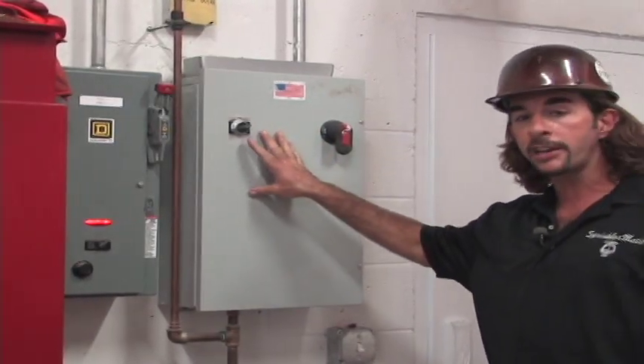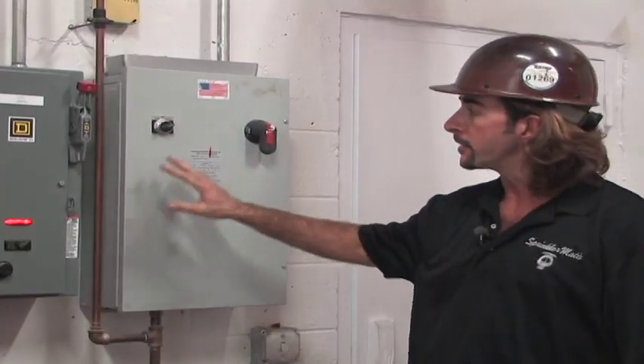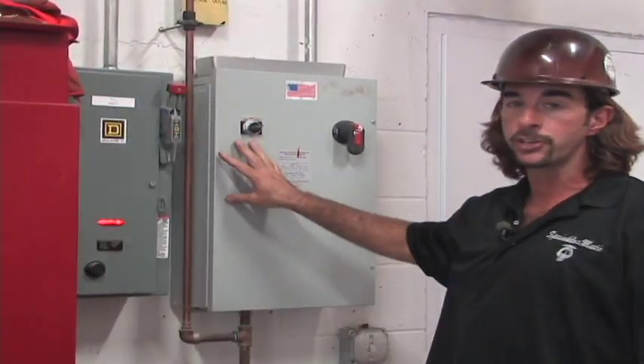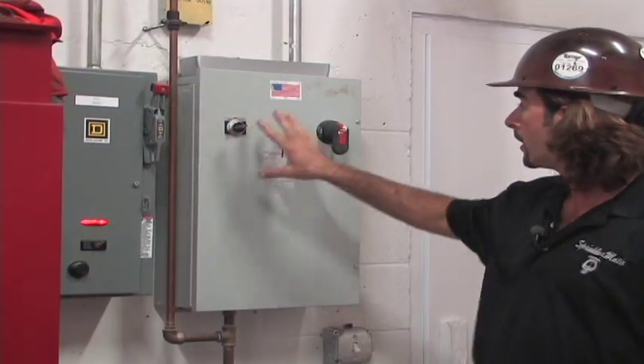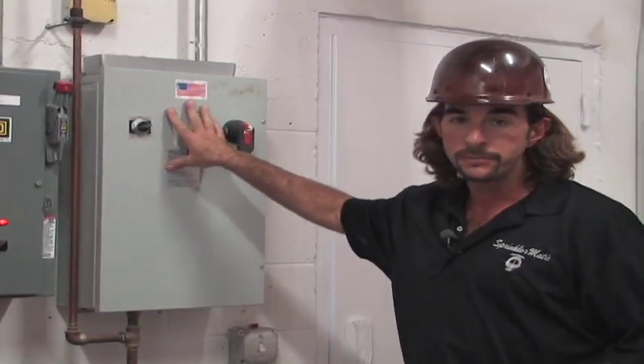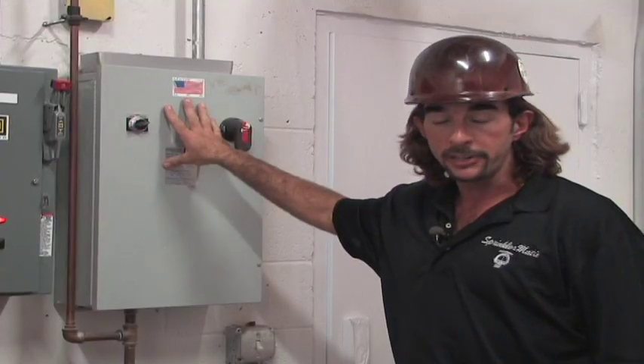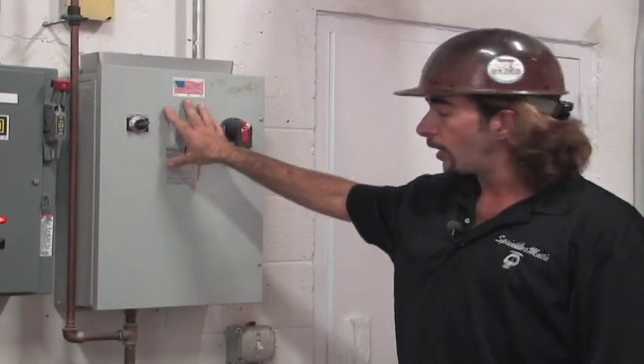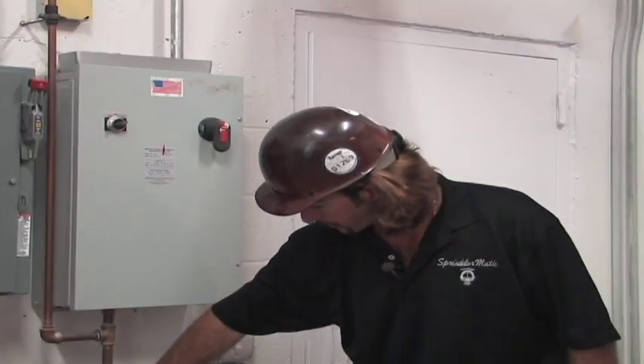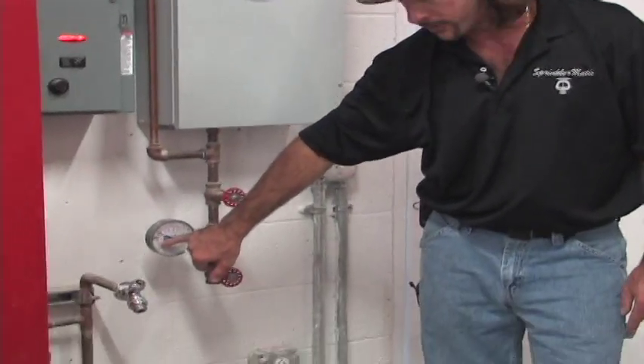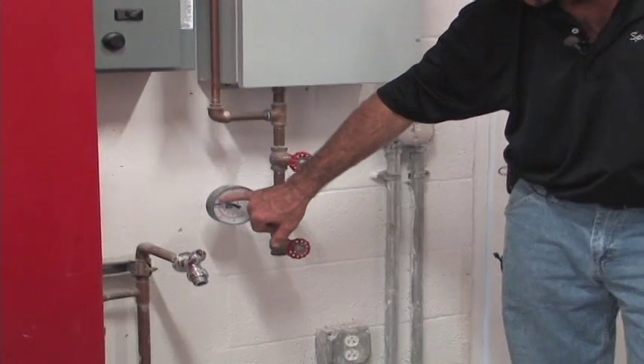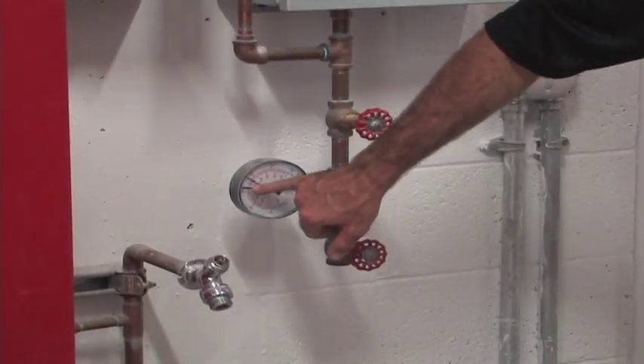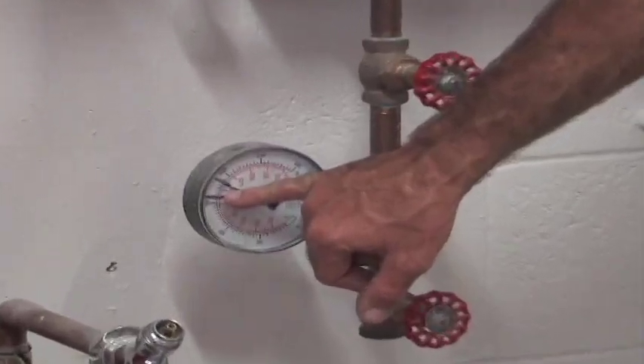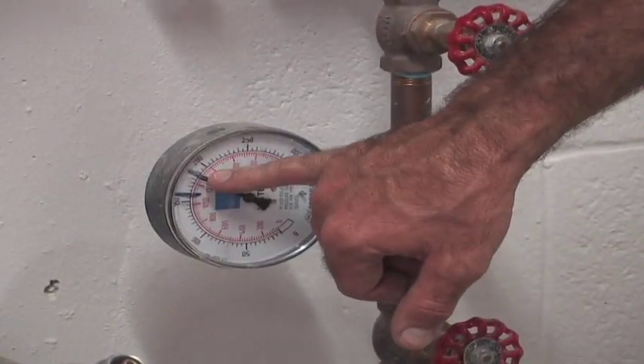This is going to be our jockey pump controller. This is going to be our disconnecting means to the controller, our main power break right here. The jockey pump controller is strictly for the jockey pump, and its only purpose is as a maintenance pump. The only purpose of the jockey pump is to make sure that the fire pump doesn't turn on. As we get down here to our pressure gauge, I've got 2 marks on the pressure gauge, and this is going to be our start, and this is going to be our stop. As you can see, when we get to 160 psi, the jockey pump's going to kick on, and it's going to stop at 180 psi.